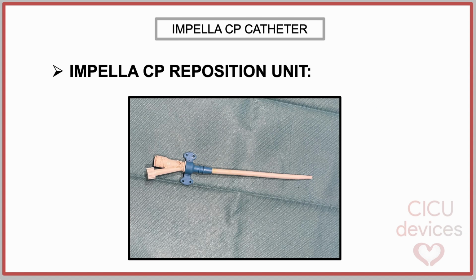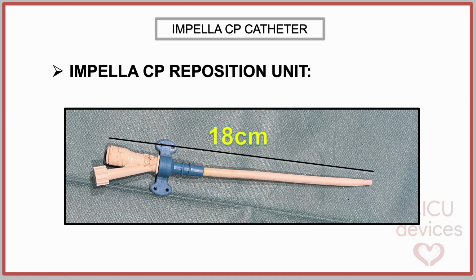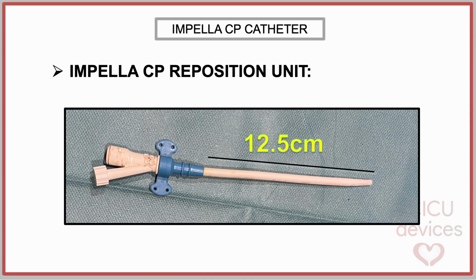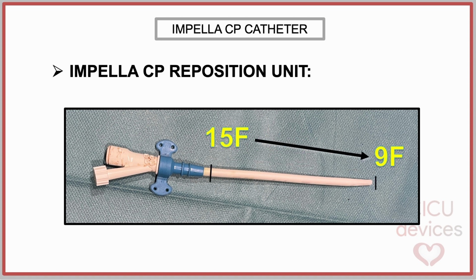The repositioning unit of the Impella CP catheter is composed of a sheath, a guide wire access port, and suture pads. The sheath has a total length of 18 centimeters, with 12.5 centimeters remaining beneath the skin and within the arterial vessel. A gradual taper from 15 French to 9 French allows the sheath to closely conform around the catheter shaft, minimizing the risk of thrombus formation and protecting against limb ischemia.